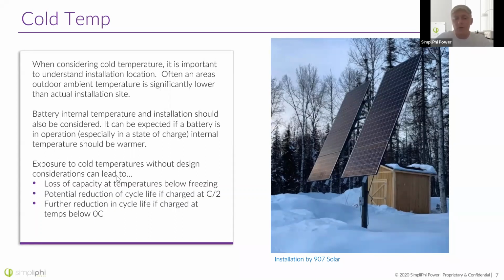Note that if your batteries are installed in a cold environment and you did not consider that in the design at all, it can lead to a loss of capacity at temperatures below freezing. This isn't huge—maybe 25%, maybe 10%, depending on the weather. It can reduce the cycle life if you're charging quickly at very low temperatures, and reduce it even further if charging well below 0.